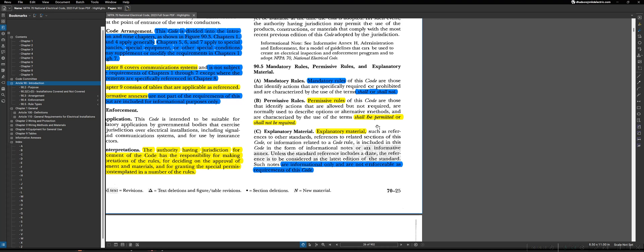In speaking on the rules of the NEC, it's also worth noting that the NEC is often referred to as a minimum, meaning you have to do at least what the NEC tells you that you have to do, but you can go above and beyond the NEC. For instance, as just a rough example, if you take a typical installation where the NEC says you need a number 10 AWG conductor for that termination, there's nothing per se to stop you from using an 8 AWG in most circumstances. Another installation may be wherein the NEC says you only have to install two ground rods for a given service, there's nothing to stop you from installing a third ground rod. Or if you take the earlier example I provided wherein I said the NEC doesn't require any receptacle outlets to be installed in an office, however, every office you've been in has likely had receptacle outlets installed, even though it wasn't code required.